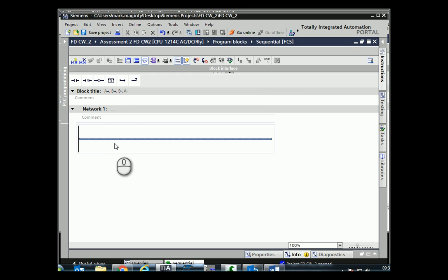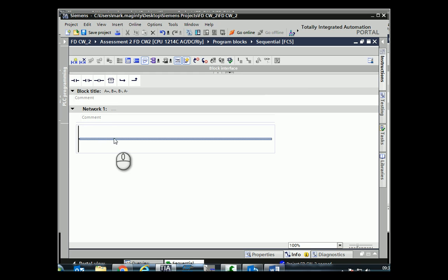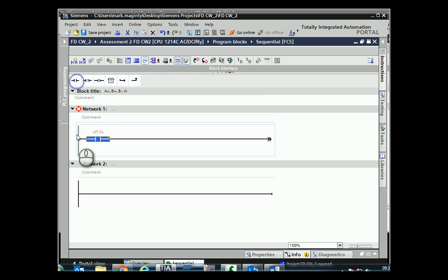The sequence A+, B+, B-, A- needs a starting condition. The coursework tells you it's a start button, and the stop button should turn things off when pressed. We need a start-stop maintained circuit — something that latches itself on and stays on until the stop feature turns it off.